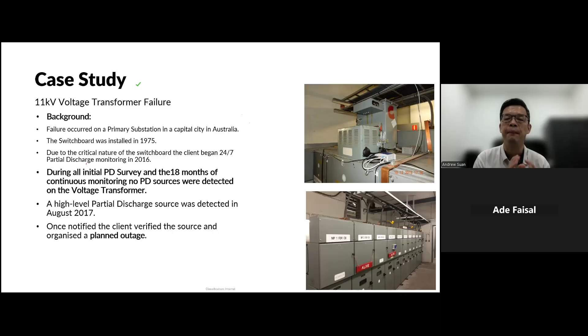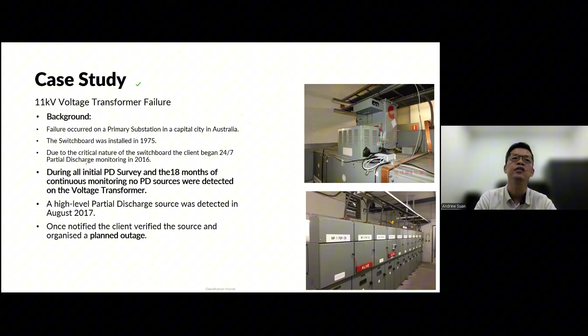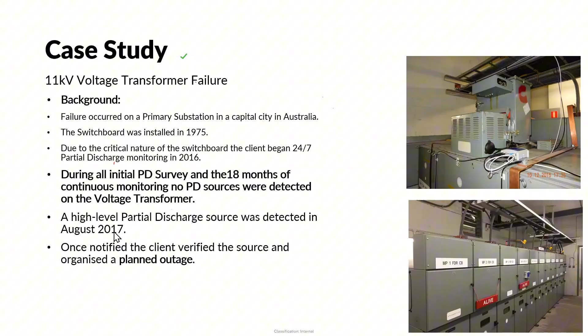In that case, since I cannot change the switchgear, I had better invest in a 24/7 partial discharge monitoring system. So I'm monitoring on a 24/7 basis, and if anything happens, I'll be the first to know. During the initial PD survey and 18 months of continuous monitoring, no PD was detected on the VT, nothing. So it's very good, near to 50 years old, such switchgear still going strong.